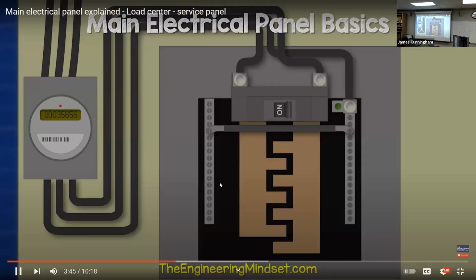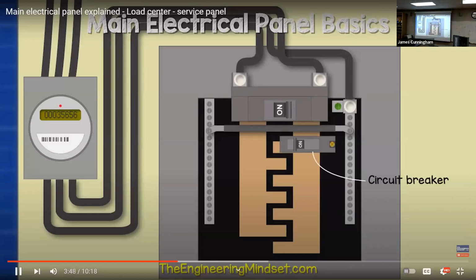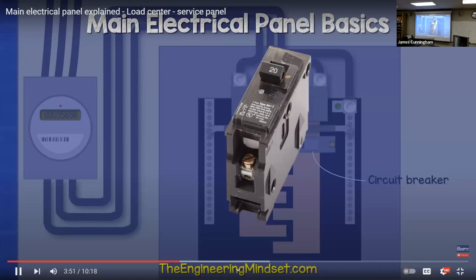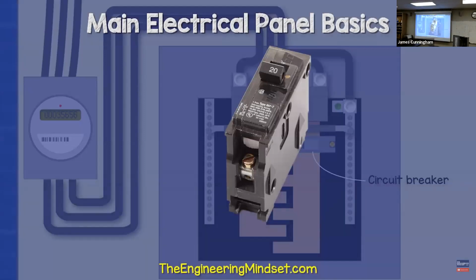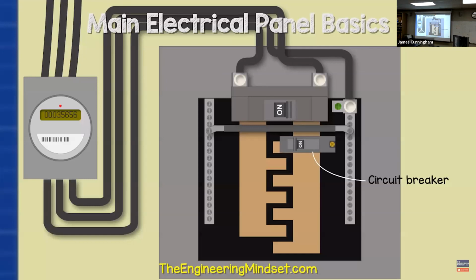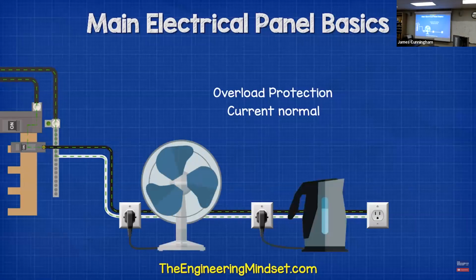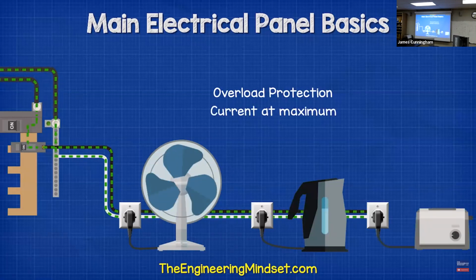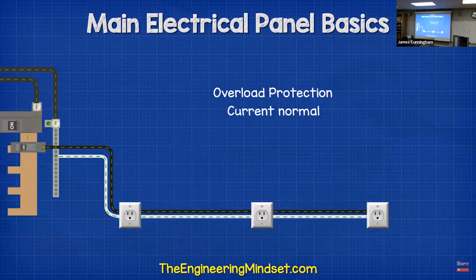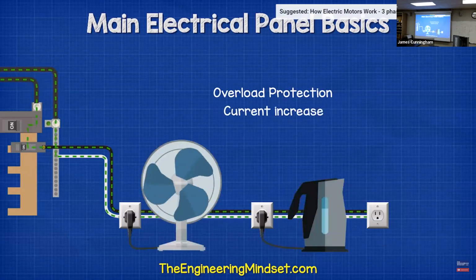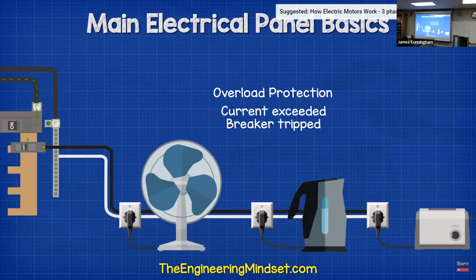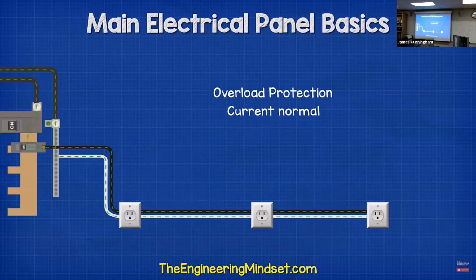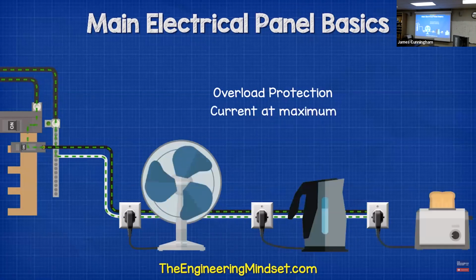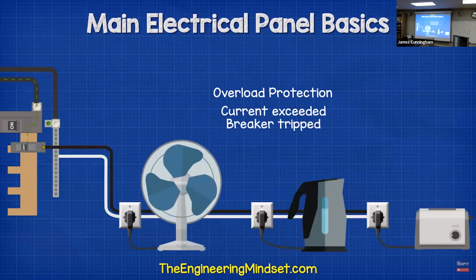Now coming back to the panel, connected to the bus bar, we'll have our circuit breakers. These will look something like this, with a black plastic casing and a toggle switch on top. The circuit breaker controls the flow of electricity into individual circuits in the property. It can be manually tripped to cut the power, but it also has 2 important features. The first feature is overload protection. The circuit breaker is rated to handle a set amount of electrical current. When appliances or lights are connected to the circuit, they will each increase the current in the circuit. If too many things are plugged in and turned on, then eventually the current will be more than the breaker can handle, and the breaker will automatically trip to cut the power off to the circuit and protect the property.